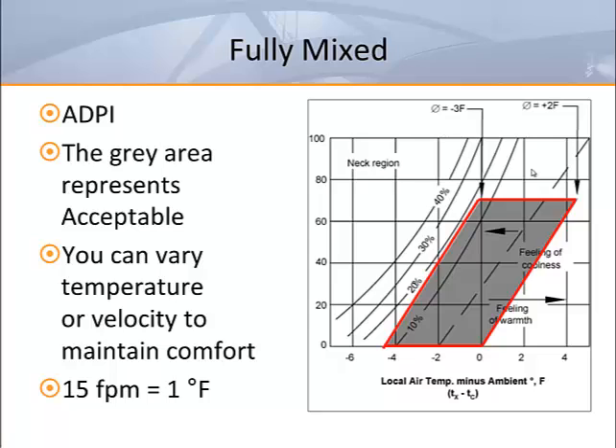While the goal is 80% or more, there is no direct correlation between ADPI and the percent of satisfied occupants. An acceptable ADPI does not guarantee comfort for Standard 55 because it does not include factors such as humidity or, in the space, the clothing or activity levels of the occupant. It does ensure a well-mixed room which meets the ASHRAE required stratification levels.